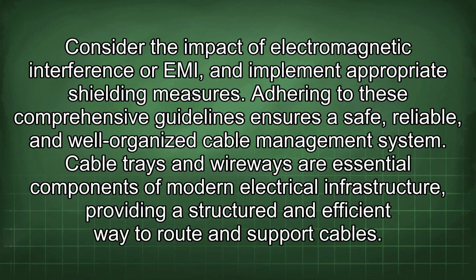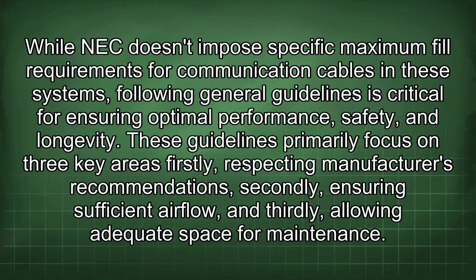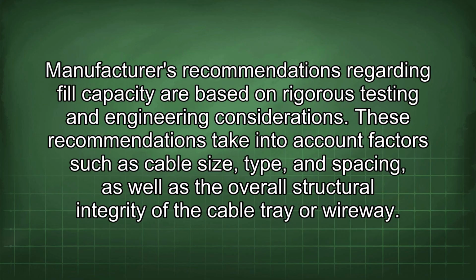Cable trays and wireways are essential components of modern electrical infrastructure, providing a structured and efficient way to route and support cables. While NEC doesn't impose specific maximum fill requirements for communication cables in these systems, following general guidelines is critical for ensuring optimal performance, safety, and longevity. These guidelines primarily focus on 3 key areas: firstly, respecting manufacturers' recommendations; secondly, ensuring sufficient airflow; and thirdly, allowing adequate space for maintenance. Manufacturers' recommendations regarding fill capacity are based on rigorous testing and engineering considerations.